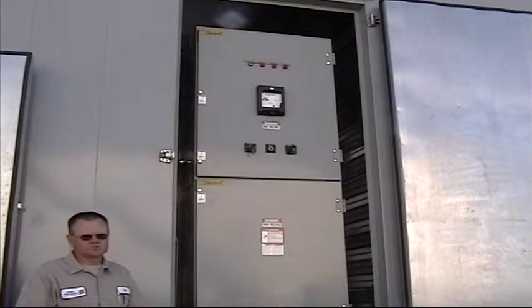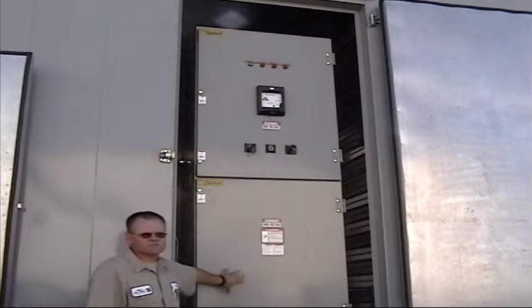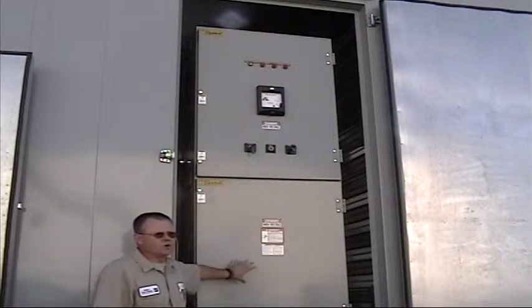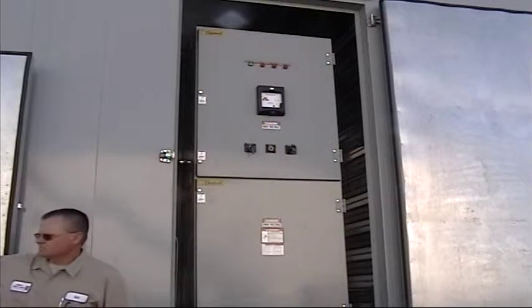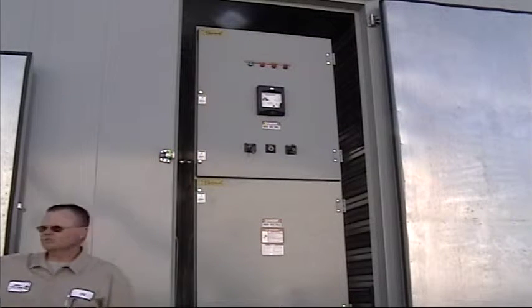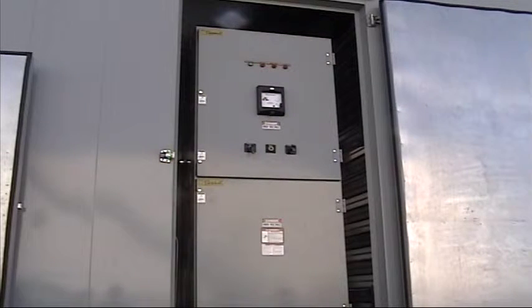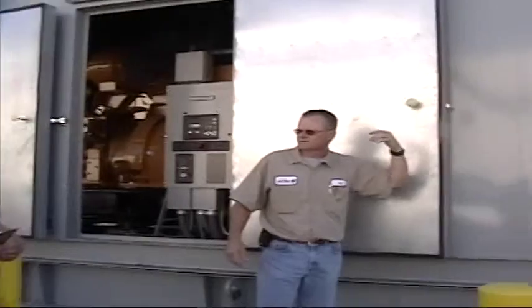Yeah, that's what I mentioned. Ground fault protection. An easy way to see this without really even opening this door is there's a mechanical switch wired to that SCADA annunciation, so you should see breaker closure. If you don't see breaker closure, you open this door, you walk in here, you don't see this red light lit for breaker status, and you see an open, then your next step would be to walk over here, open that door, and make sure you don't have a fault. Make sense?